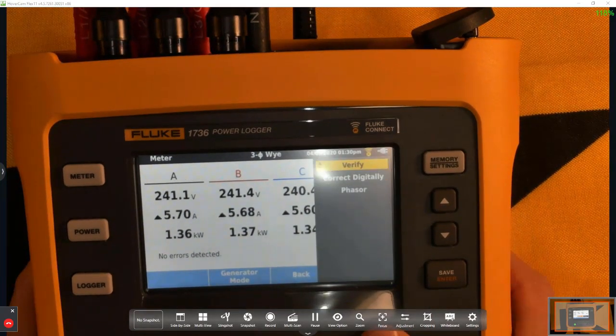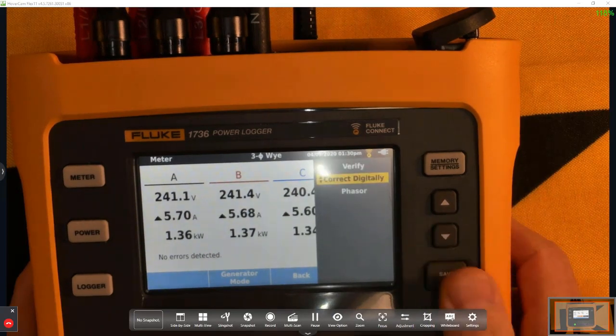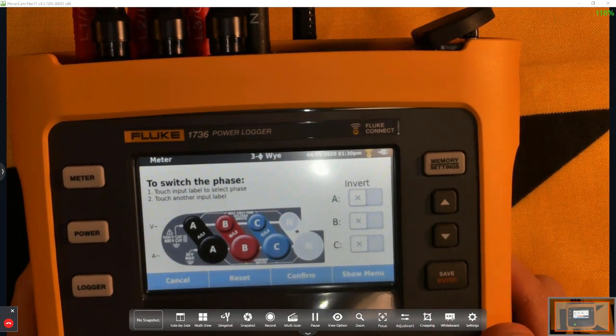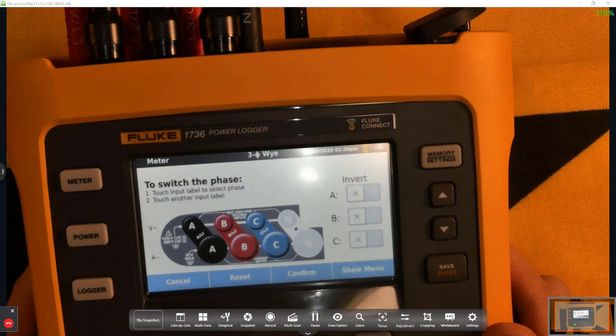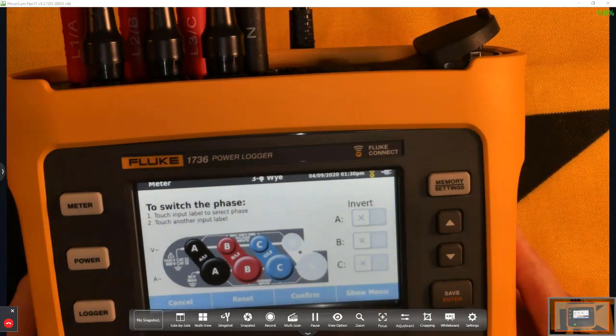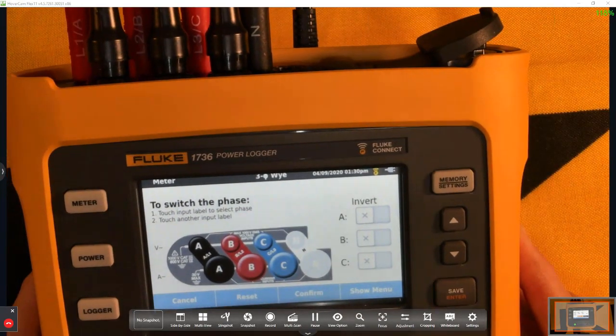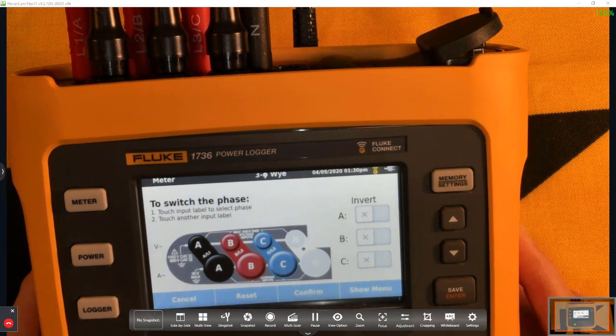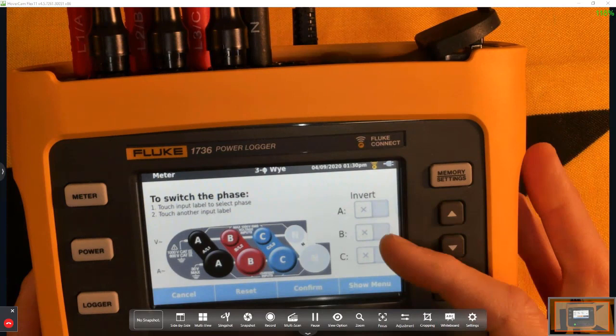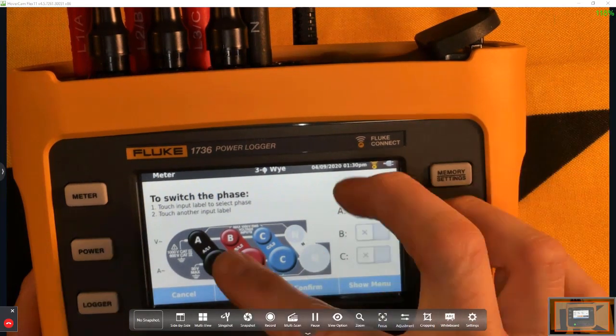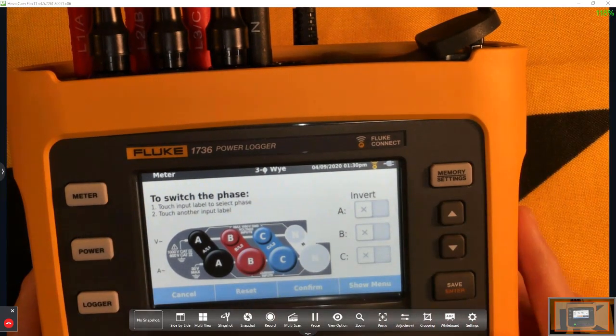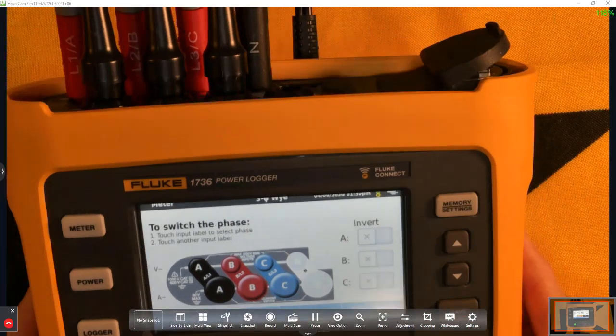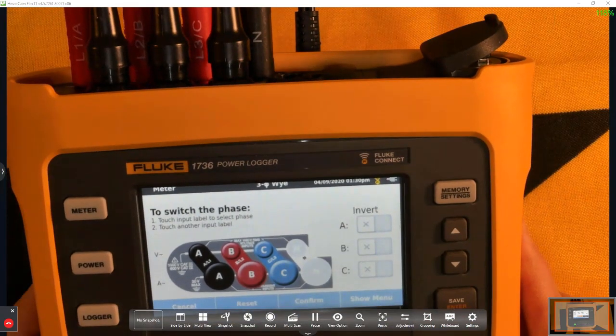If we go back to F4 here and go to correct digitally, we also give you the option to manually access and move things around. If there's been some adjustments in the panel and things can't be accessed anymore, you have the ability to reverse current clamps here, and you have the ability to swap phases here if you want to. That's one of the convenience features built into the unit.